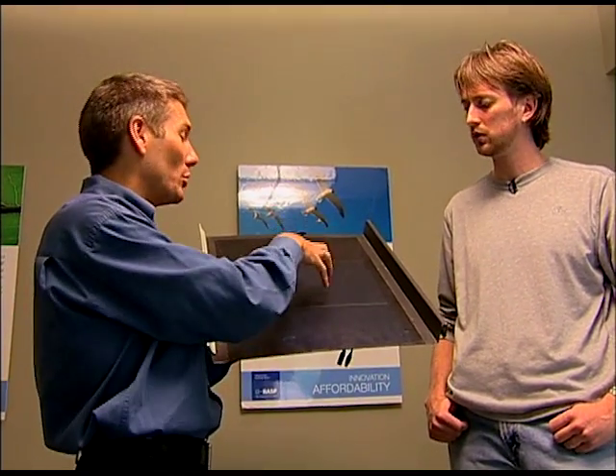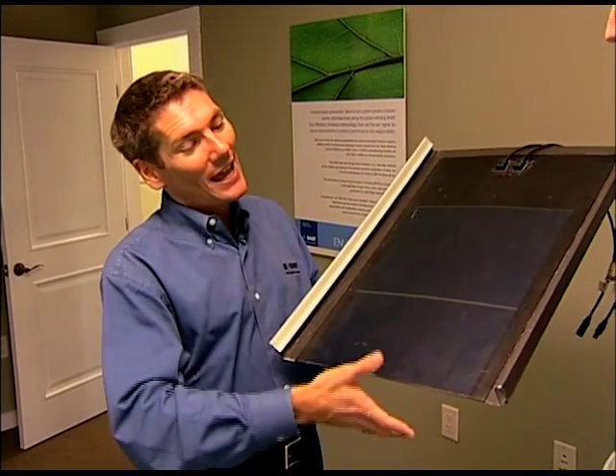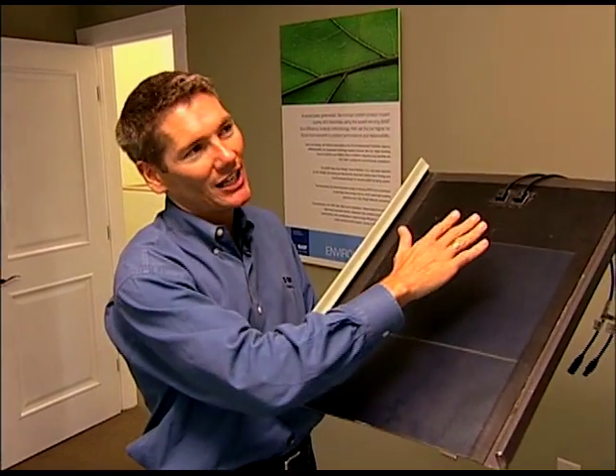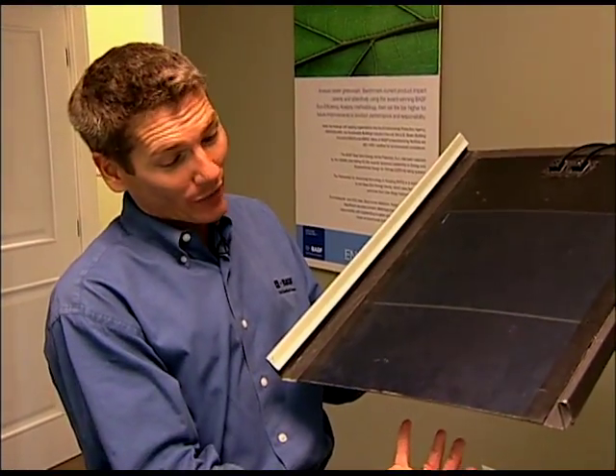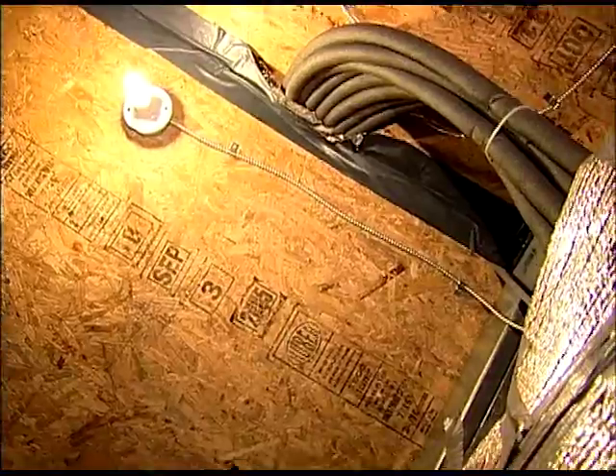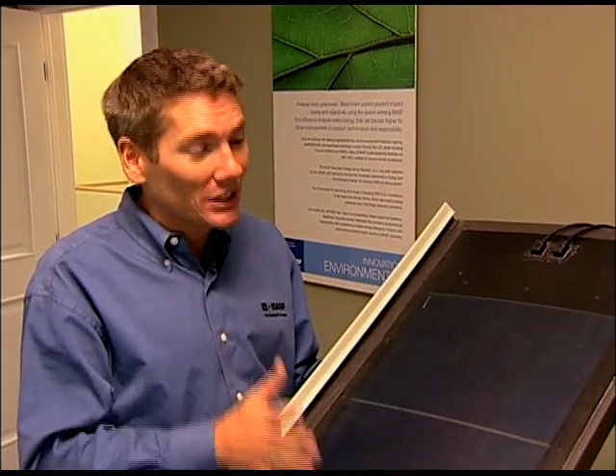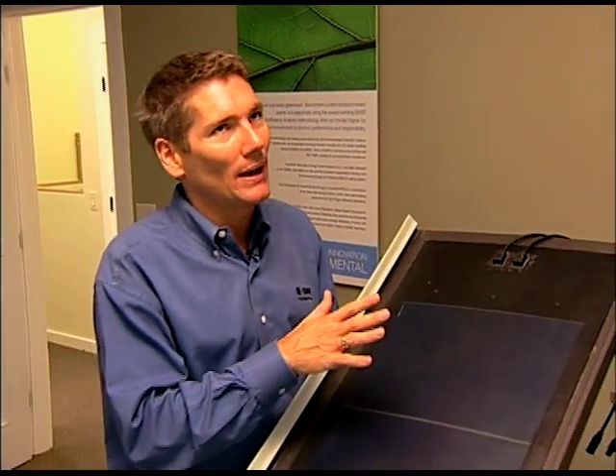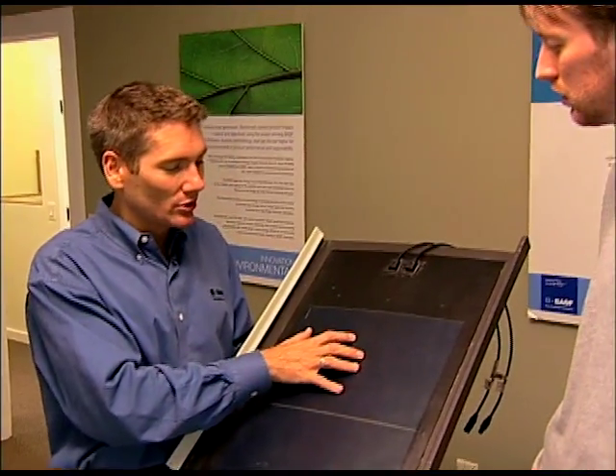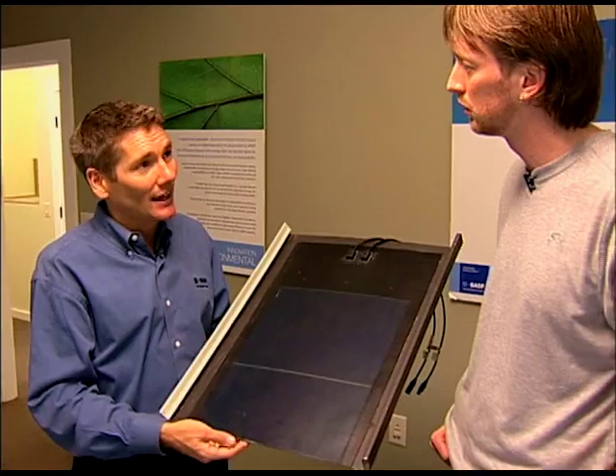So it's kind of a photoelectric on top, thermal hot water system on the bottom, and if you had a big panel here shading the roof, then the roof wouldn't get hot and you couldn't heat the hot water. But the hot water from the roof will come down during the summer months as much as 180 degrees Fahrenheit, and in the winter it'll preheat the water to about 80 degrees Fahrenheit. So it really is a quite interesting system. So all in all, for the house here we have about 2.5 kilowatts of electric, 4 kilowatts of thermal, so for a total of, what is that, 6.5 kilowatts total.